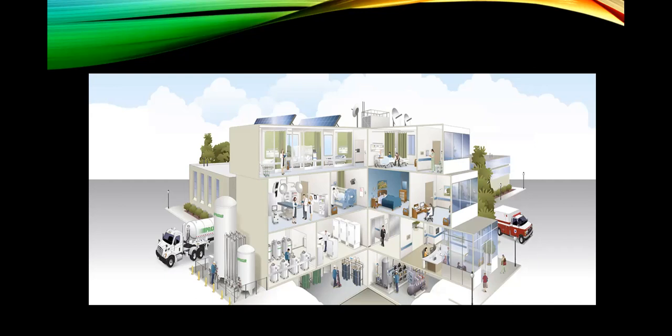We have zones where there's a little open glass window with pipes inside. You open up that glass and they have a lever that cuts off the oxygen, the air, or the vacuum, right? Because if it gets too high or there's a fire in the building, we're going to go cut that off because oxygen supports combustion and makes it worse, right? So the fire chief will say, go and turn that off. Who do they tell that to, the nurses or respiratory? Respiratory. Respiratory is responsible for cutting it off.